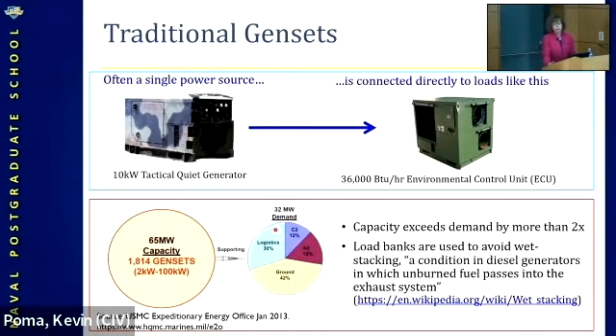So why are they oversized? Because just in case there is growth, a need for more power, we make them bigger than they need to be. But this comes with a penalty: the efficiency of this generator is much lower when the load is lighter. So the lighter the load, the farther away from the rating of the generator, the more fuel you burn.